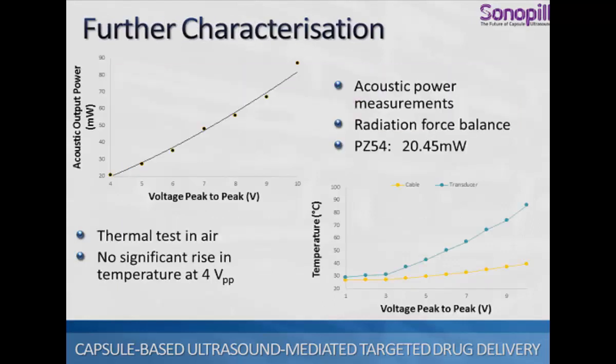So we've now carried out further characterization of the PZ54 transducer. So we carried out acoustic power measurements using a radiation force balance, and at 4 volts peak to peak, we found an acoustic power of 20.45 milliwatts. And we then carried out some thermal testing to make sure the transducer doesn't overheat during use significantly. So this thermal test was done using a thermal camera focused on both the transducer and on the coaxial cable. And it was done in air because if it didn't overheat in air, the idea is that it wouldn't overheat in water. So this graph shows the temperature of the transducer at different input voltages. And neither the transducer nor the cable overheats significantly at 4 volts peak to peak. However, the temperature of the transducer began to overheat after this.